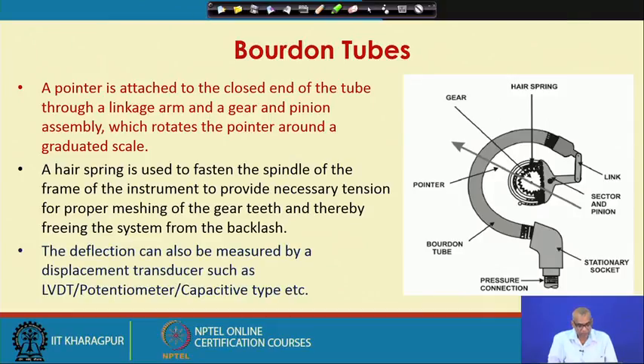The deflection can also be measured by displacement transducers, and we have studied such transducers, such as the LVDT, linear variable differential transformer, or potentiometer, or capacitive type transducers. So, the deflection ordinarily we are reading by the movement of the pointer against the scale, but you can also attach an LVDT or potentiometer or capacitive transducer to the tip of the Bourdon tube, so that you can read the displacement of the tip of the Bourdon tube using such an electromechanical displacement transducer.